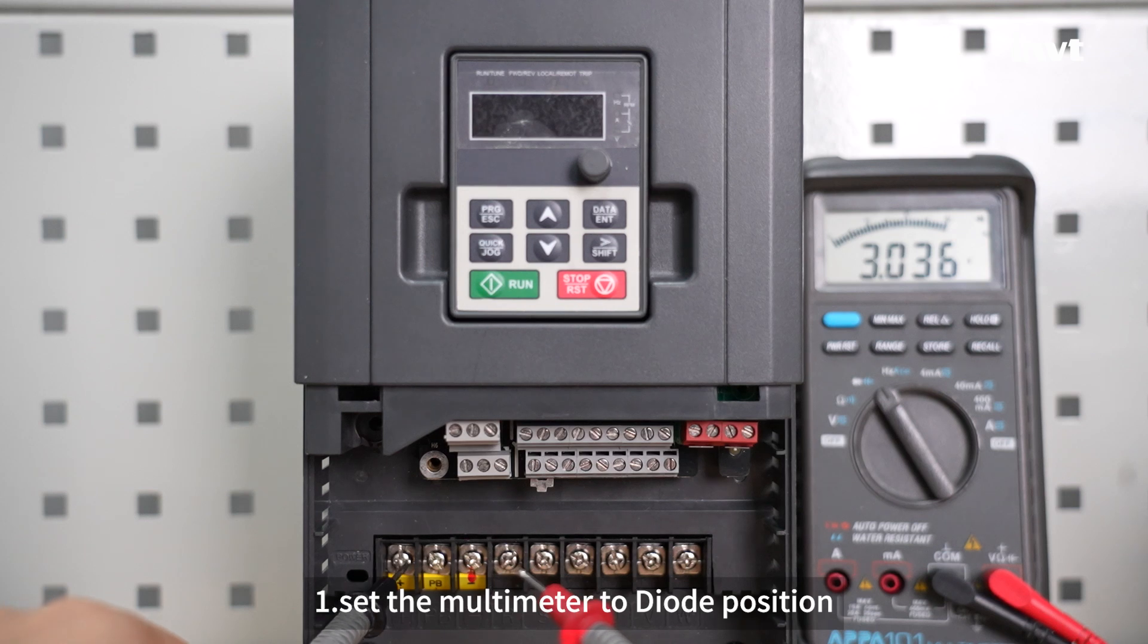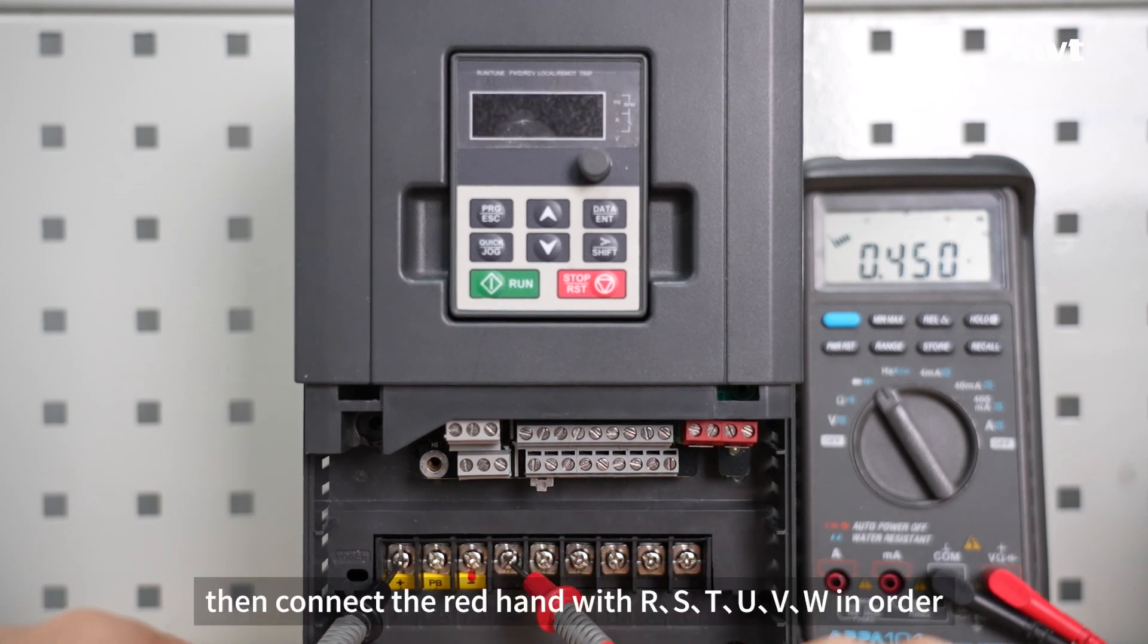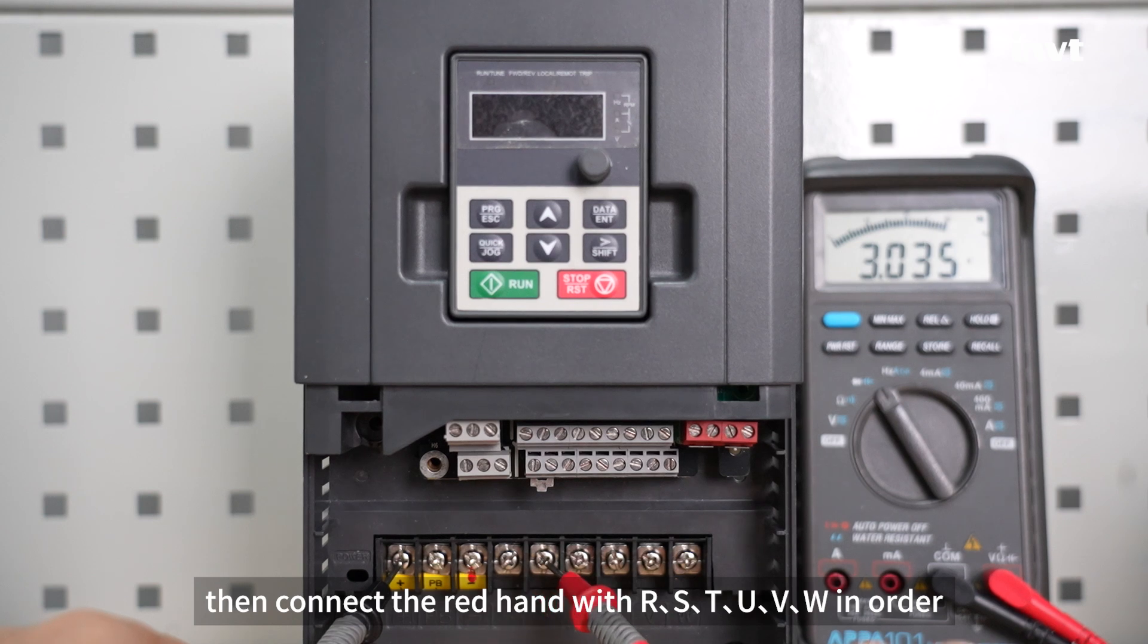First, set the multimeter to diode position, connect the black probe with plus. Then connect the red probe with RSTUVW in order.